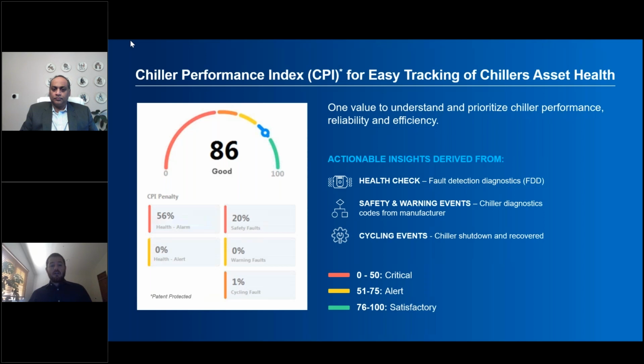The next thing we look at are the safety and warning events. This is really important, because I'm always asked, what's the difference between connected chillers and my BMS system? This is a big differentiator. A BMS system gives you about 20 points, more or less, from the chiller — that's great for command and control. But with connected chillers, we're able to get deeper into the data. When we connect to the chiller, we're pulling out over 200 points from that chiller, including the chiller diagnostic codes from the manufacturer. It's literally like standing in front of your chiller, having view into it 24/7.